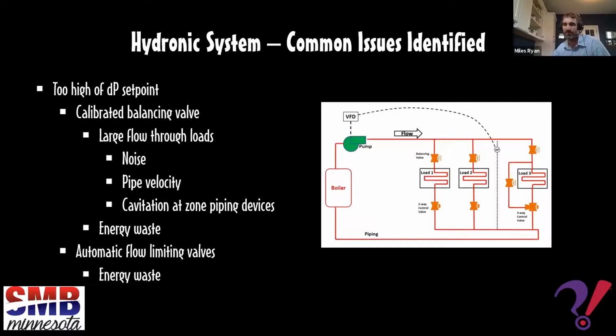you're wasting energy. Now, an example of having an excessive differential pressure set point for a system that employed auto flow limiting valves is something I recently encountered. I came to a building, and basically they had those auto flow limiting valves installed on all of their coils. However, it was a pretty mild day, and I went into the mechanical room and I noticed that the pump was operating at full speed. It was operating at 60 hertz. And I kind of just thought to myself, that seems odd, but we were doing functional testing of the system. I knew I was going to get to it eventually and figure out why.